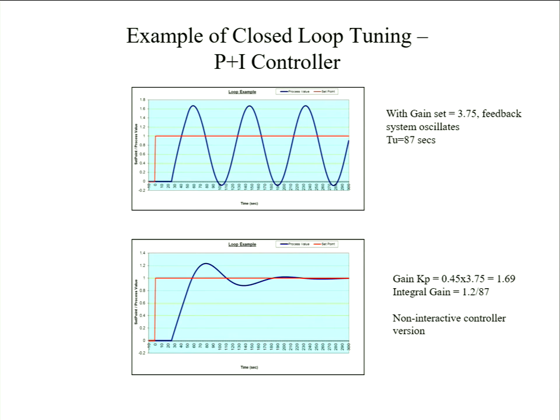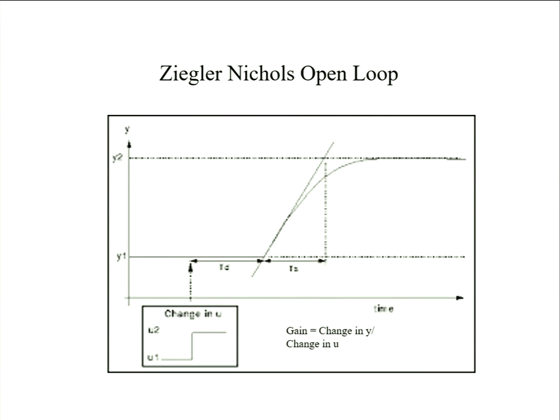So you're basically taking that line up there and estimating another time constant, and you're also interested in the gain, which is how much the output changed for a change in input. So if I move by 5% and it moved by 1 million, well, I've got 20 million per 100%. You don't necessarily need a big change, but it's got to be big enough to be measurable and discernible beyond the noise in the measurements. But you can keep it controlled. You can operate within well-defined parameters.